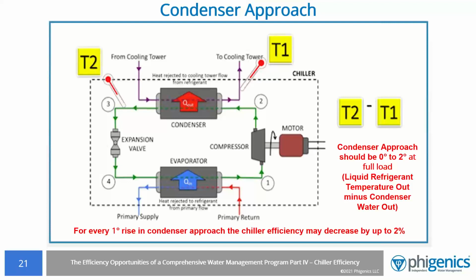If necessary, you may need to ask your teenager for some help on the formulas. So, condenser approach, you heard Larry talking about it. One of the most common problems we see, and one of the easiest to identify, is condenser approach. Condenser approach is the difference between the temperature of the water leaving the condenser and going to the cooling tower, or T1, and the temperature of the liquid refrigerant leaving the condenser going to the evaporator, or T2.